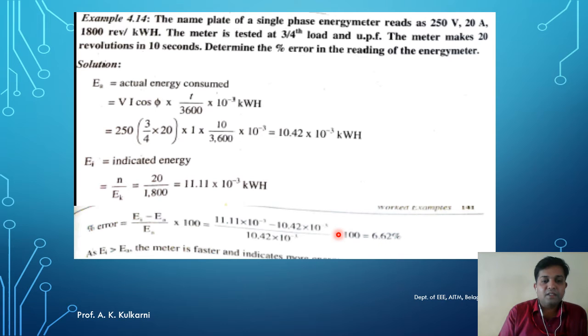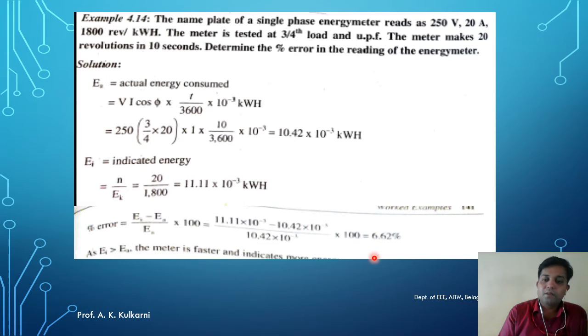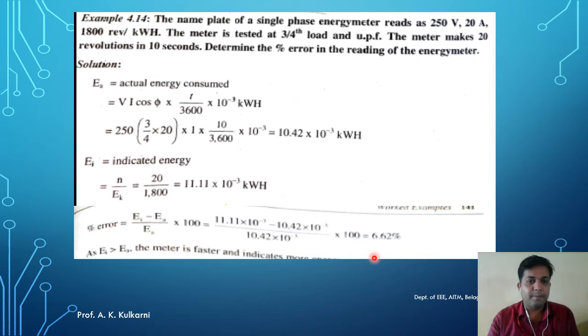The indicated energy is greater than the actual energy, which means the meter is running faster and indicating more. This means the energy meter is not calibrated properly. In this way, we calculate the actual energy, indicated energy, and the percentage error of the energy meter.